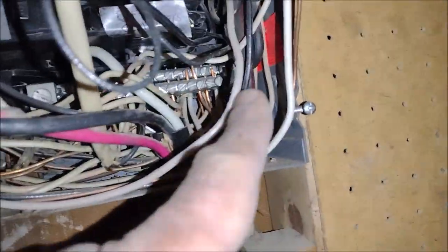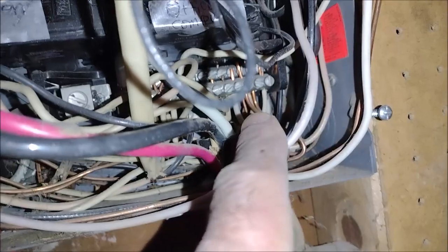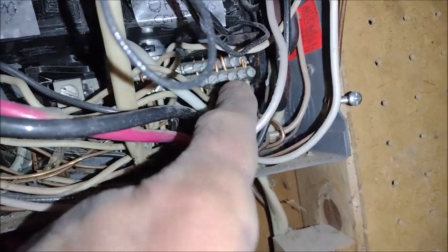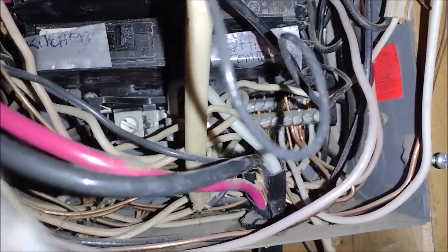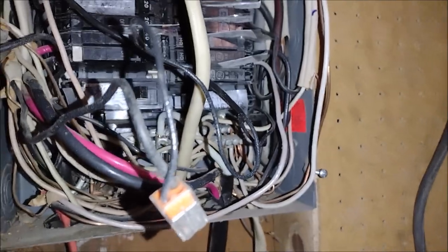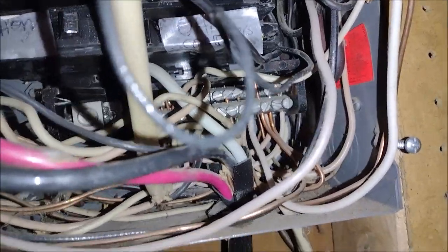Where do they fit here? If you look here, you discover that the white and the ground, both of them are connected to the same metal bar that is grounded. So you will ask, why do we have to have neutral and ground? Here the neutral and ground are the same thing on the relay box.